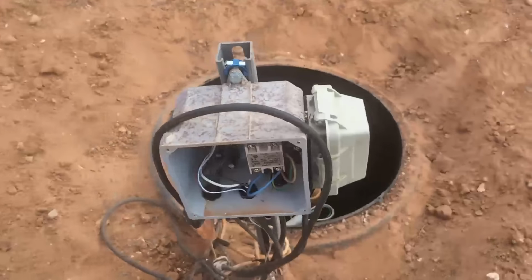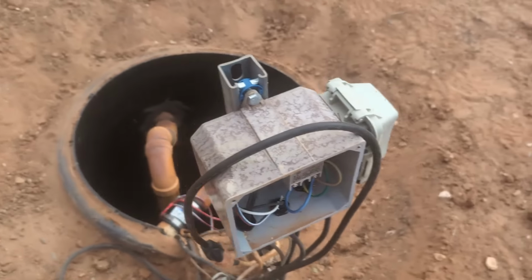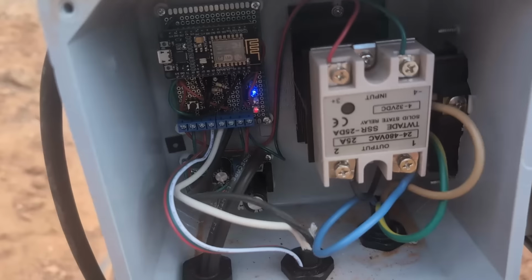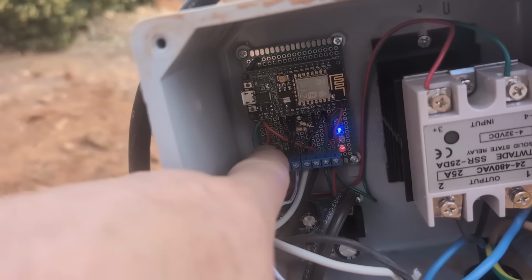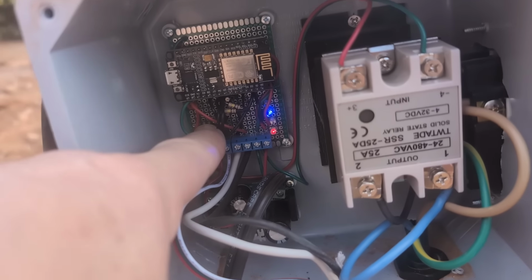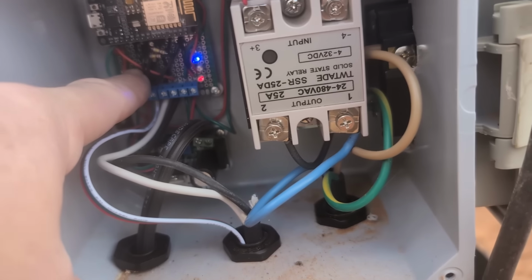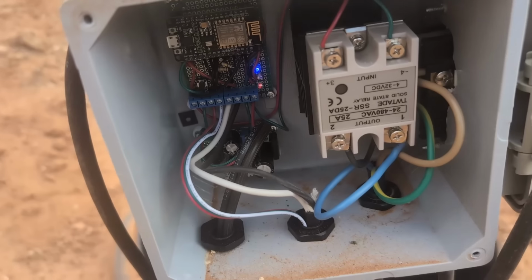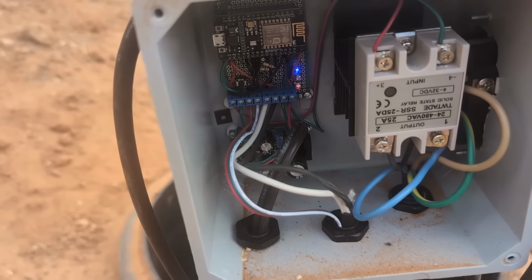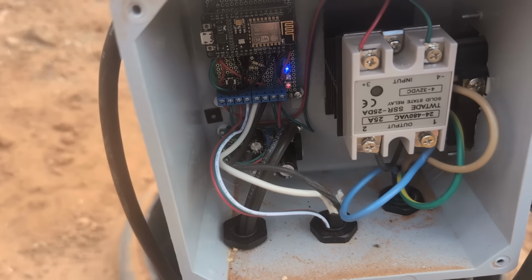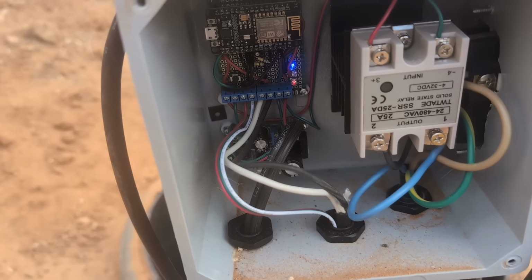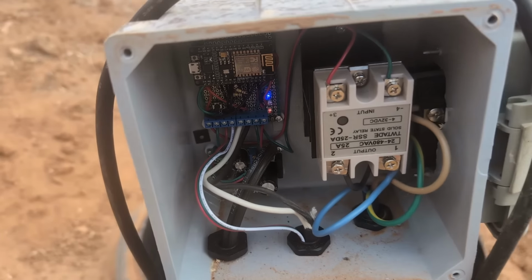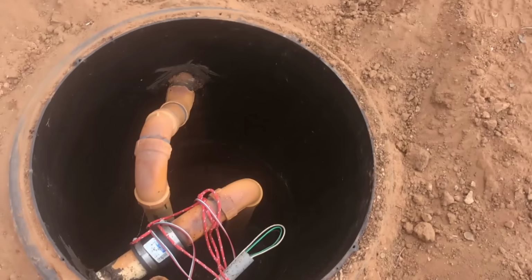In my enthusiasm, I was sure that everything was fine because there wasn't standing water, but this little black button, when I press that, I'm supposed to hear the sump pump come on. I'm not hearing the sump pump come on. It's dead. So thank goodness the lid is dry. We don't have to pump out that water, but that sump pump down there has either rusted for not being used, or it's clogged with stuff that's not supposed to be down in there. So dang it, we're going deep.